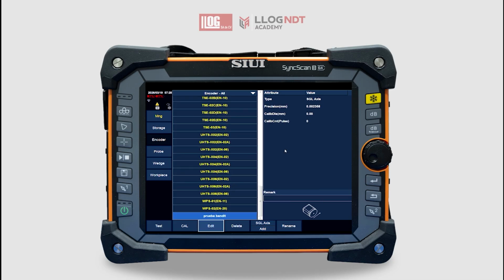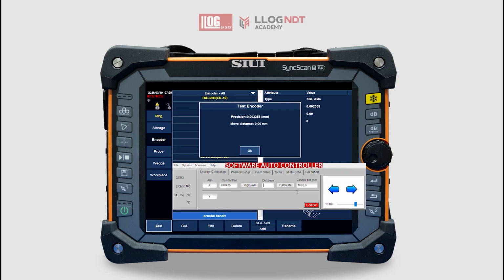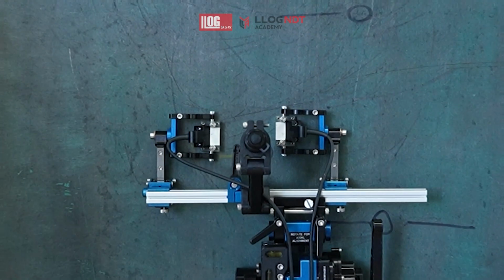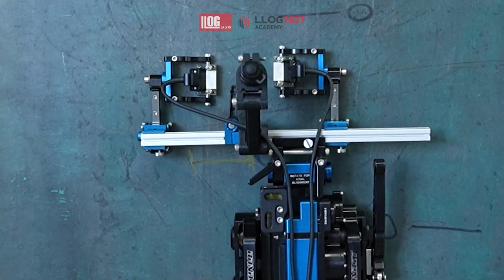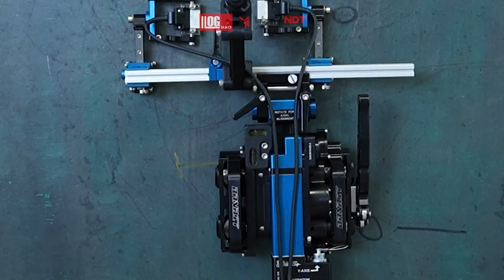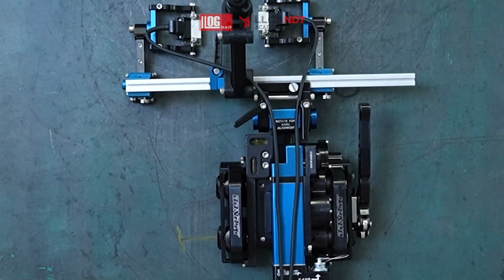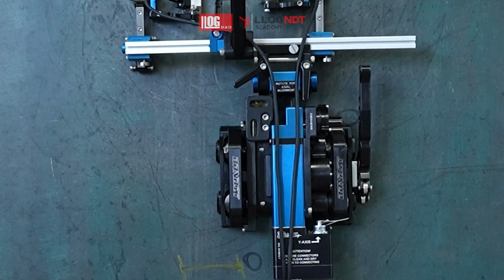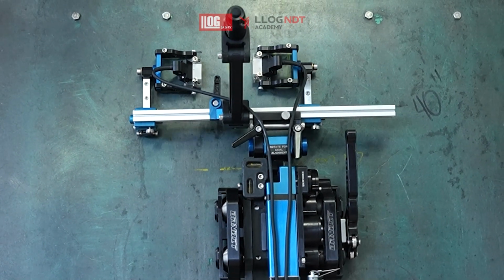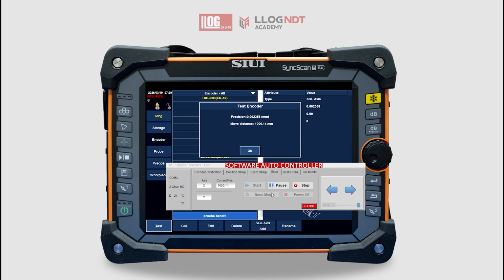Finally, select the configured encoder. Then, perform a test to verify the distance traveled by the encoder. Set the distance to 1 meter and place the encoder at the starting position. Once the travel is complete and the same distance is confirmed on both the instrument and the software, scanning can begin.